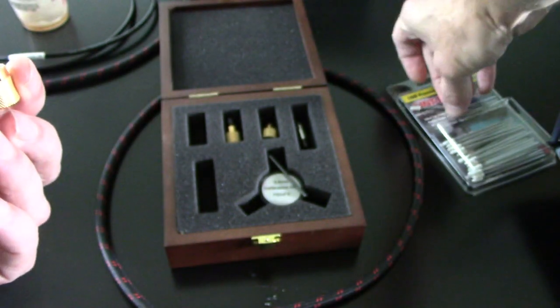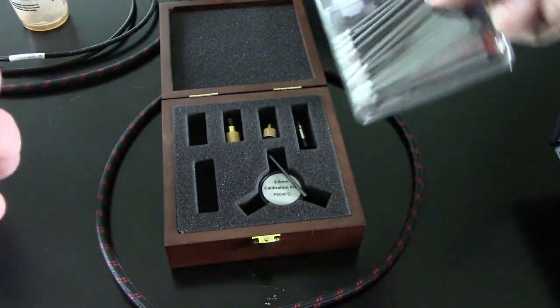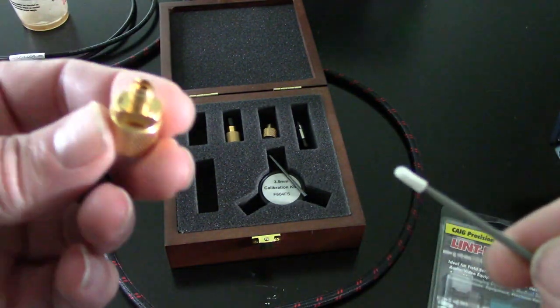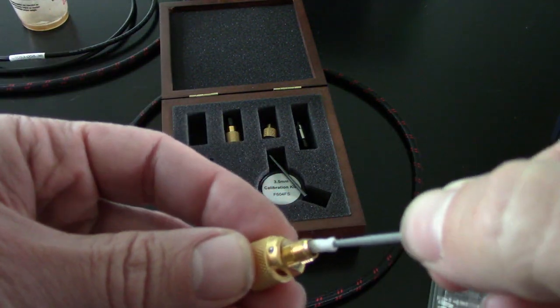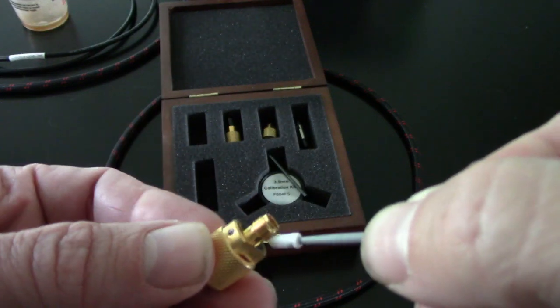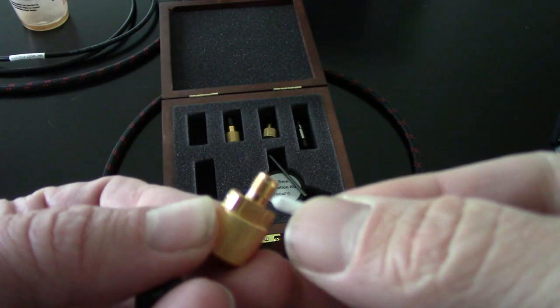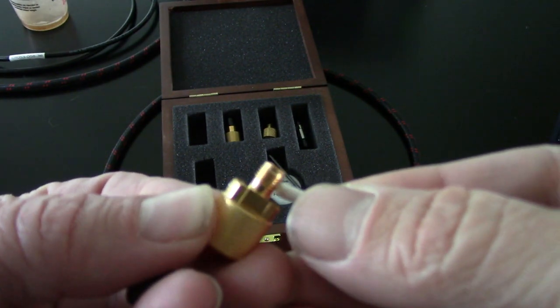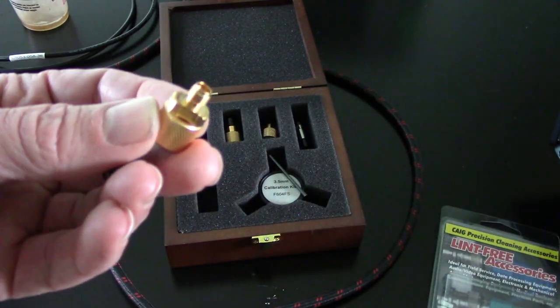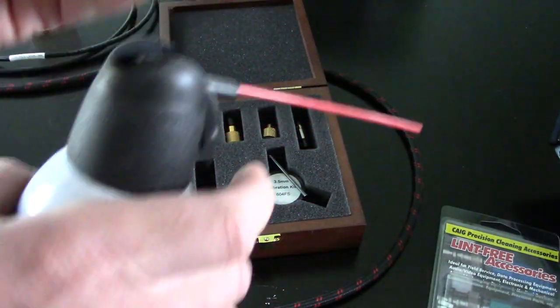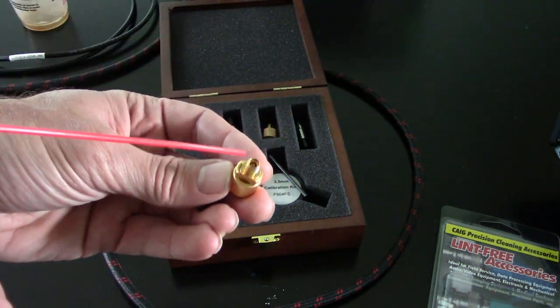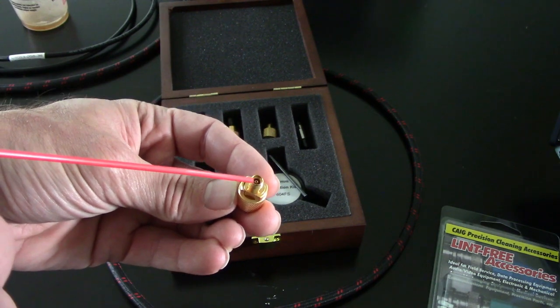Here we've got some lint-free swabs. We're going to put some isopropyl alcohol on and we're going to swab around the interior of that connector, that center conductor, and also the threads. We could also use the tip of the swab to get into the threads. After we've cleaned we can take our compressed air and give that a quick shot just to blow off any residue from the IPA and get any dust off of it.